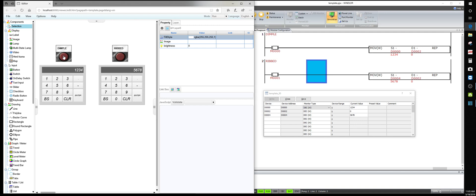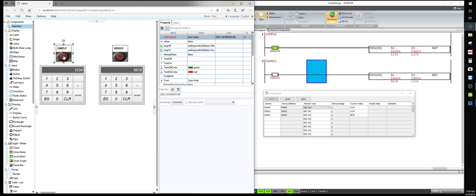Right now nothing is in the destination register D2. D2 is where you do a compare to make the machine stop or shut something off. Now when I hit the Dimple button, it moved 1234 into data register D2. That's now in compare register D2. You're comparing this when the pressure transducer reading hits 1234 PSI - or whatever scaled value corresponds to that pressure in your 4-20mA analog input.